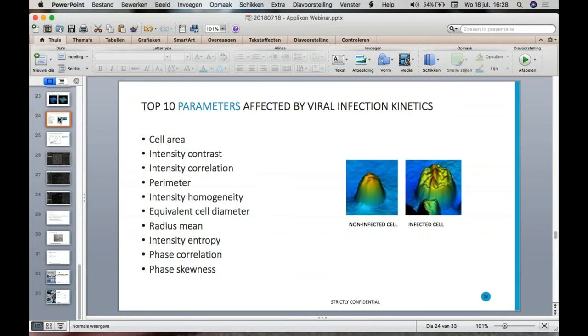Question: What is the maximum cell density Ovisio can measure? It depends on the cell type. We have experience with CHO cell cultures up to 35 million cells per ml, which is about the maximum. With SF9 cells, which are a little smaller, we expect to go higher; with yeast, which is also smaller, we can go much higher. We feel comfortable up to those cell densities, meaning we are ready for batch and fed-batch methods. For perfusion, we don't have a solution at the moment.